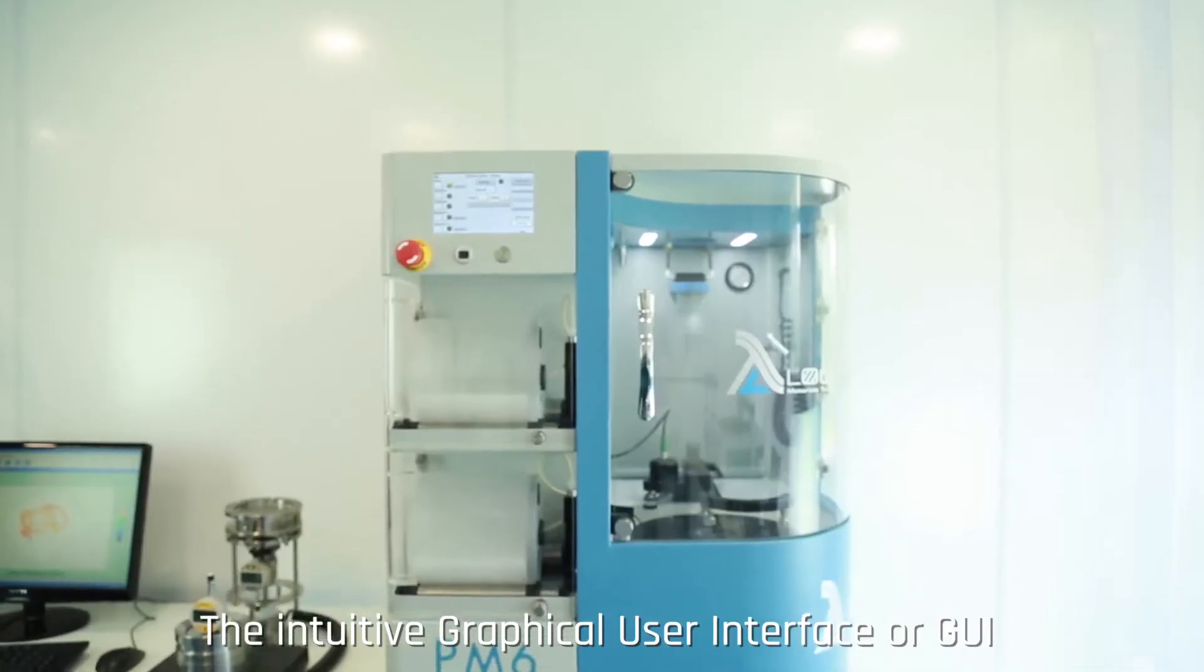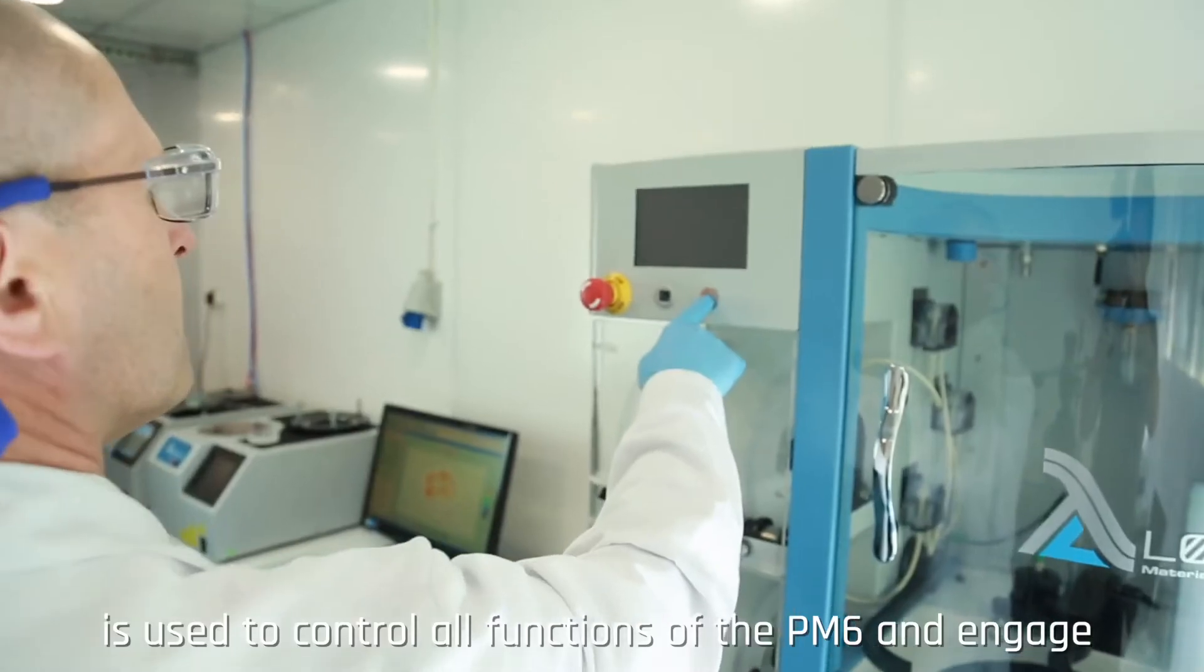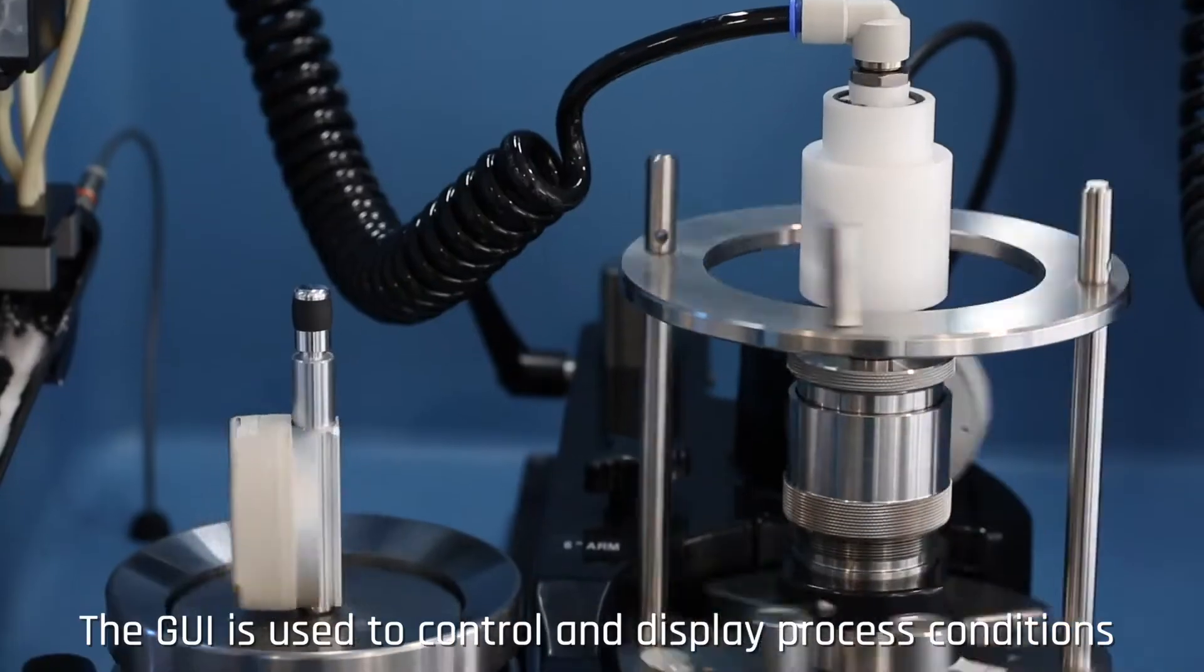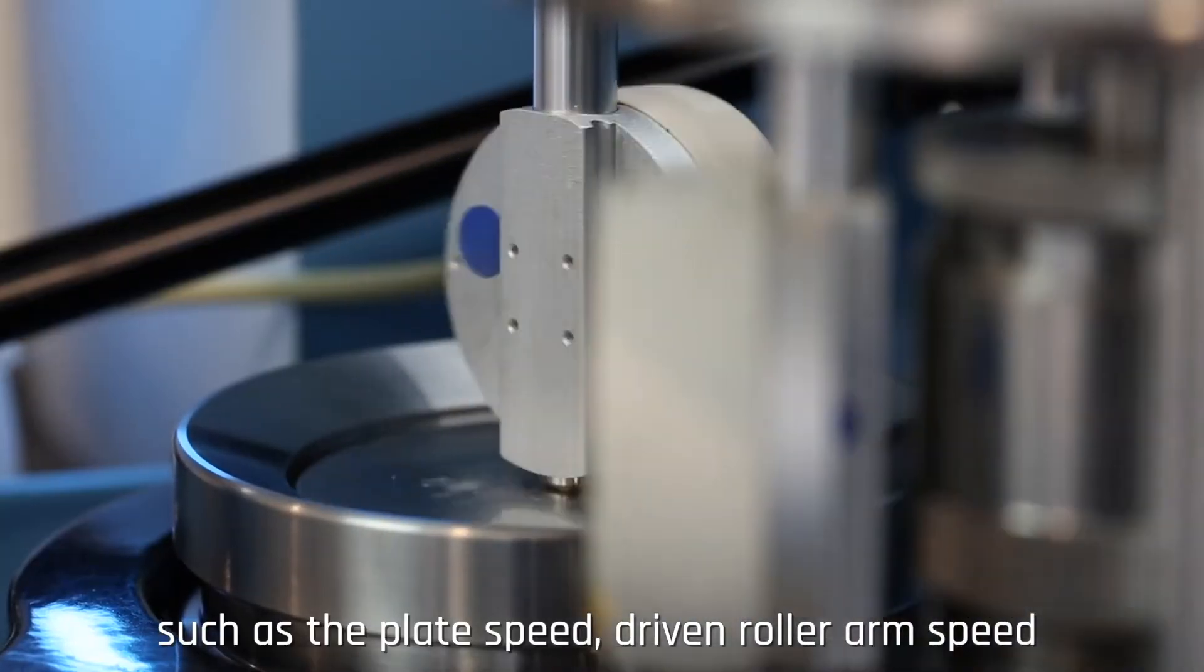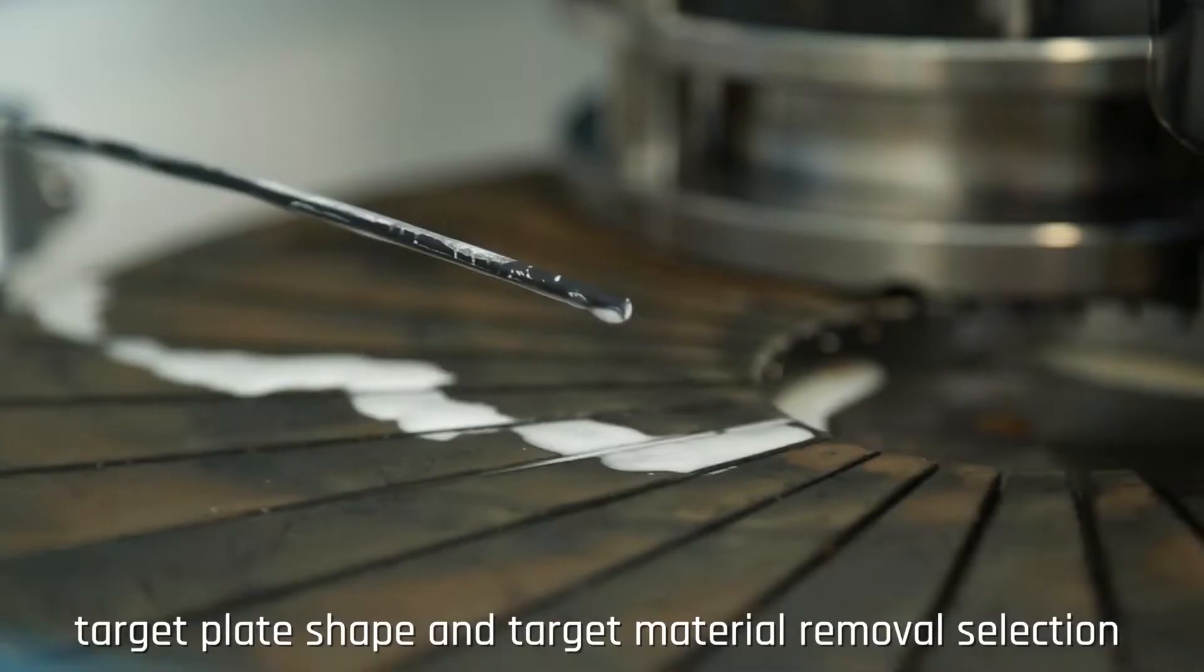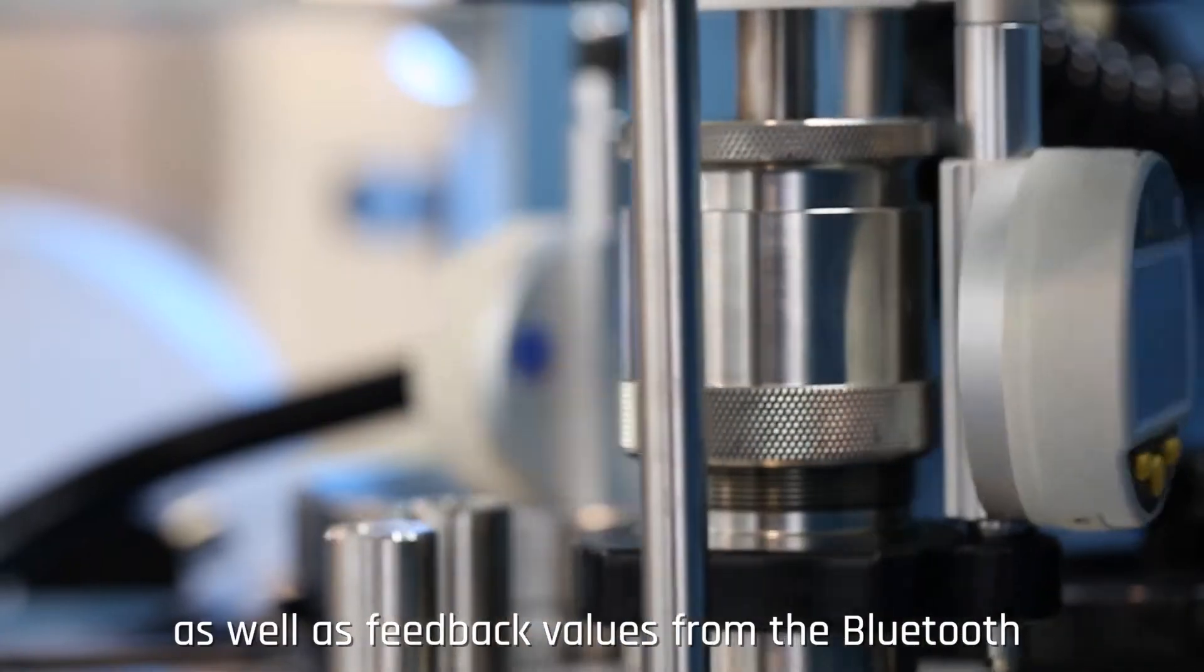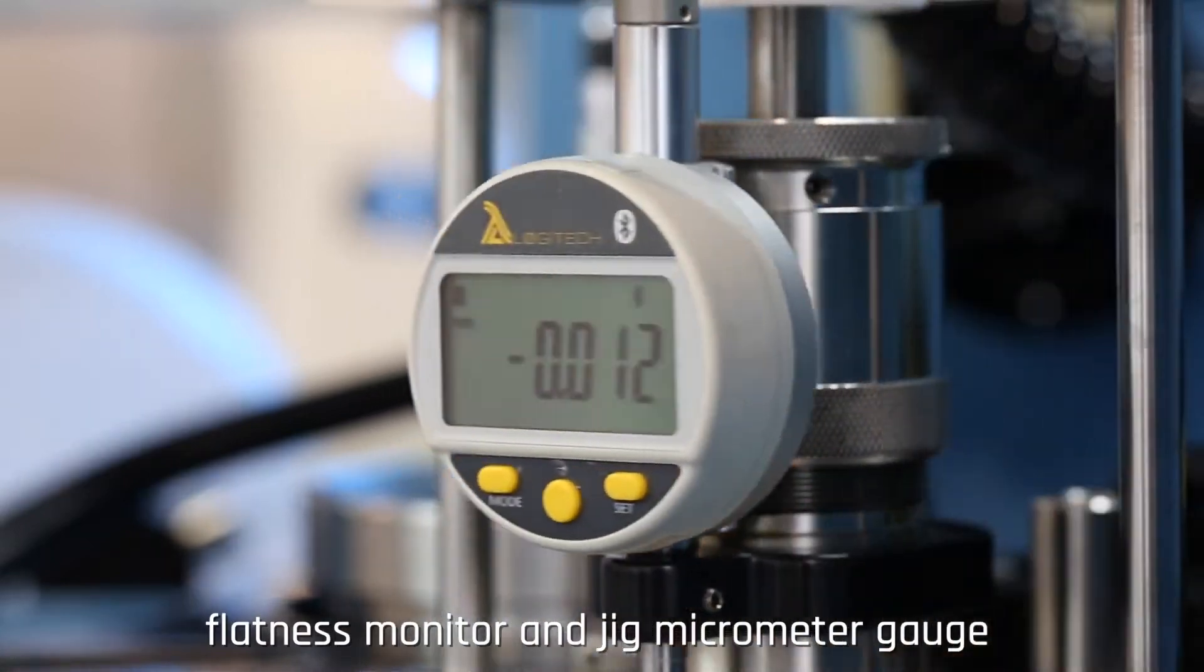The intuitive graphical user interface or GUI is used to control all functions of the PM6 and engage fully with the process. The GUI is used to control and display process conditions such as the plate speed, driven roller arm speed, target plate shape and target material removal selection, as well as feedback values from the Bluetooth flatness monitor and jig micrometer gauge.